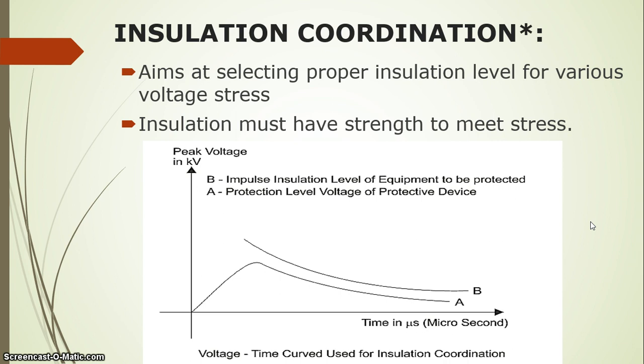In the diagram, you can see peak voltage in kV on the Y-axis and time in microseconds on the X-axis. Whenever insulation is designed, it must be tested for switching impulse level. Before that, the lightning impulse level is tested, which has a wave shape of 1.2/50 microseconds. As transmission voltage levels have been increasing, insulation must be tested for switching impulse level.